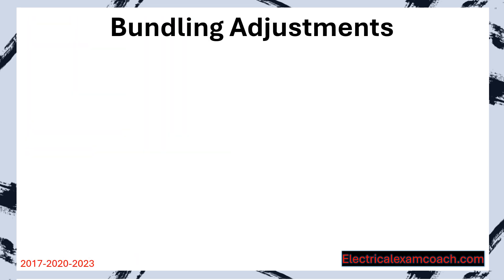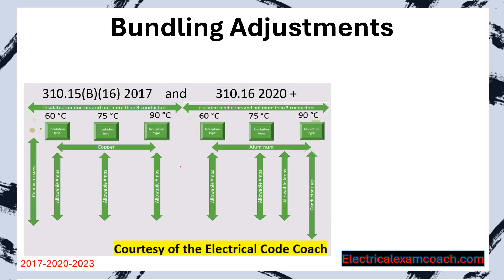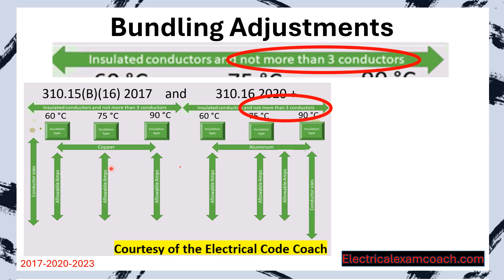Let's dive into bundling adjustments. Let's take a look at our primary ampacity table. These values in this table are true if — looking at the paragraph above the table — there are not more than three current carrying conductors inside of a cable, pipe, or even buried in the earth together.